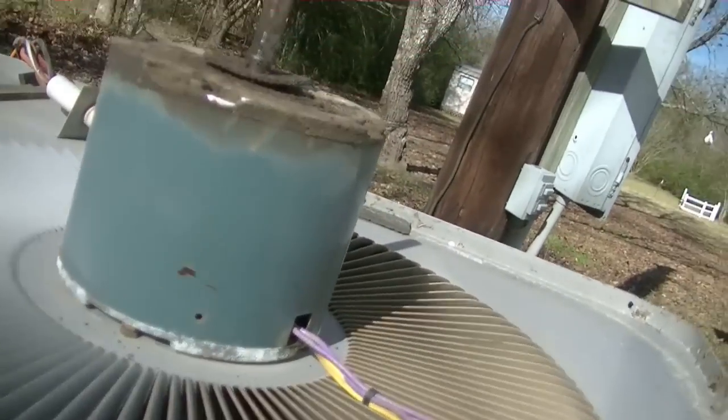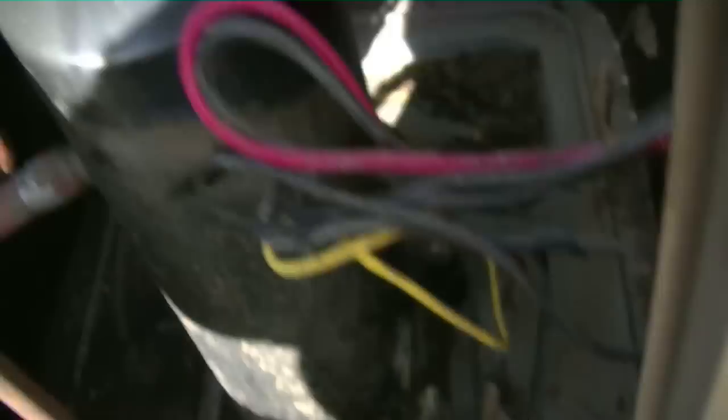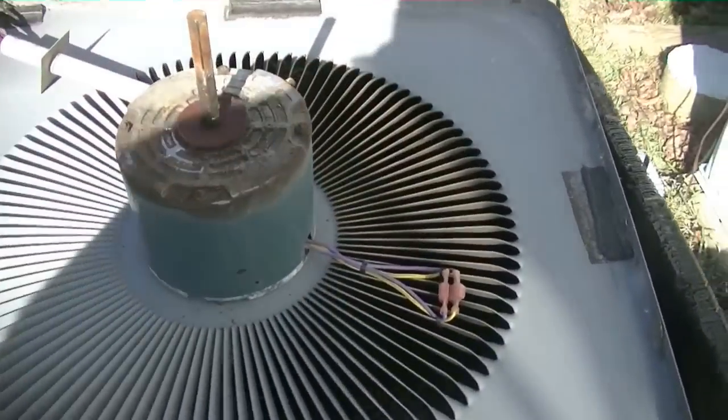As you can see, we're changing out a condenser fan motor. Got a bunch of oil right here — I thought we had a leak but my gauge shows we've got plenty of pressure. That oil could have come from the motor. I also found this discharge line sensor that's full of oil. Other than that, the charge looks about right for the temperature it is out here.